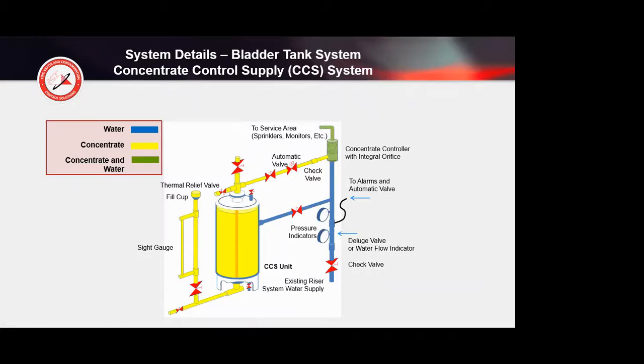I think we've done as many as 10 risers in one system. But here's a backflow check valve or an OS&Y valve. And then this is a deluge valve. So basically how this system is going to operate is the detection on the hazard could be any number of things. Could be a CO monitor, could be thermal imaging, could be Protectowire linear heat detection. So there are multiple ways that you could detect that you have a fire.